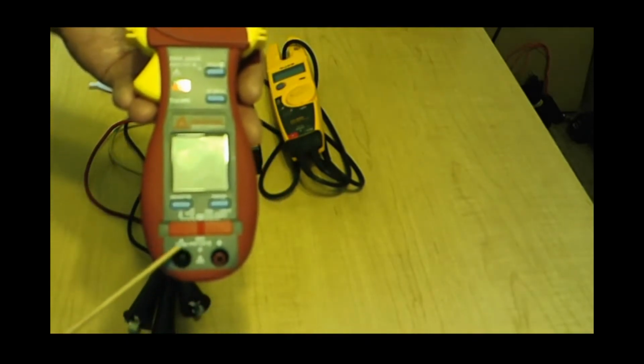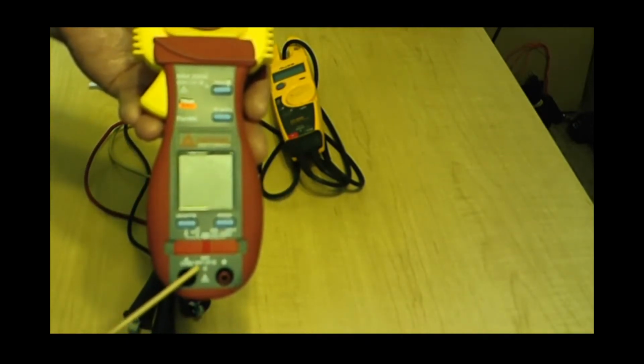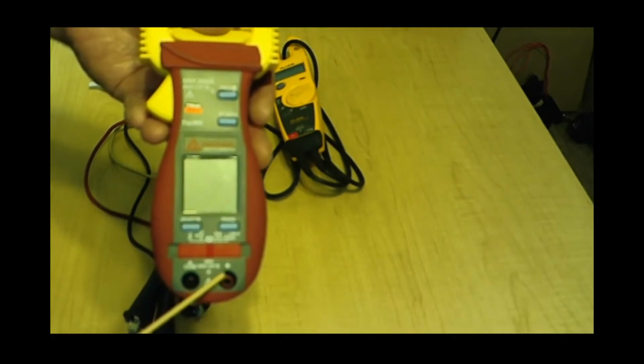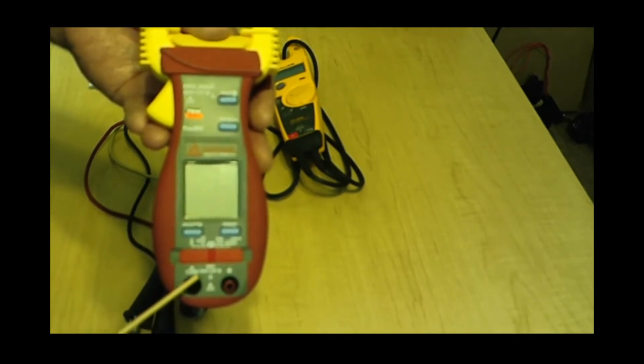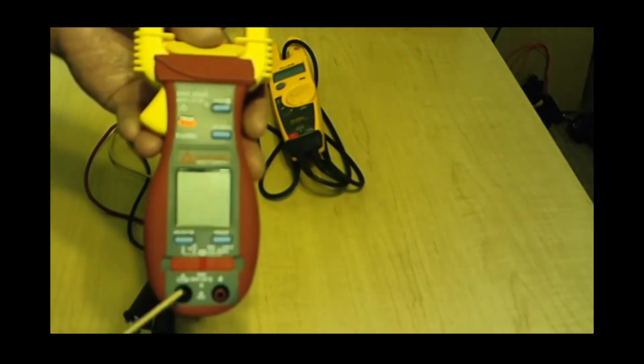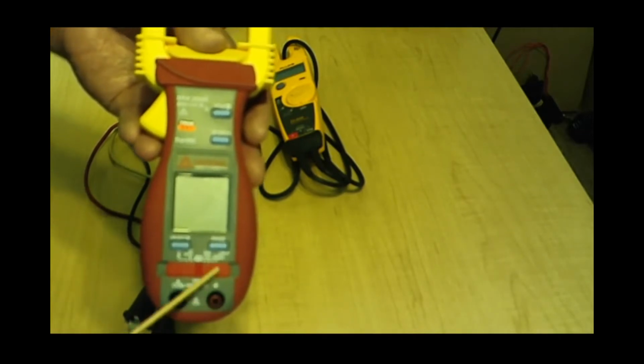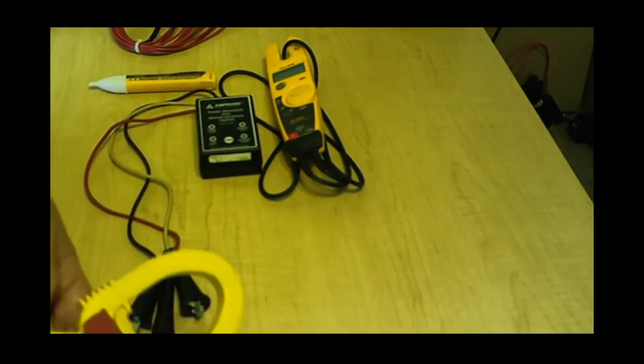Down here you have the voltage ratings. 600 volts, Cat 3. So no more than 600 volts. If you go over 600 volts, the meter will explode. Cat 3 again is the location to use the meter.